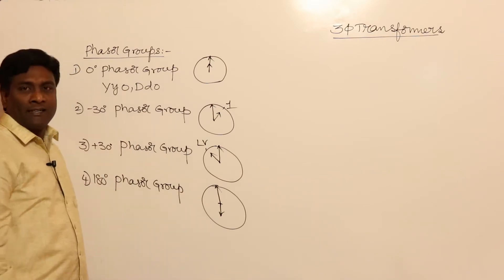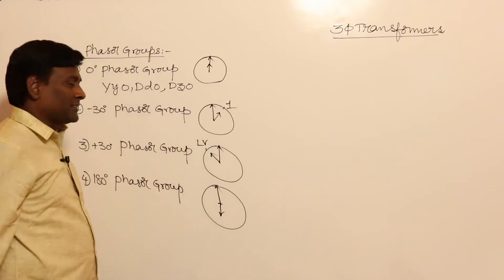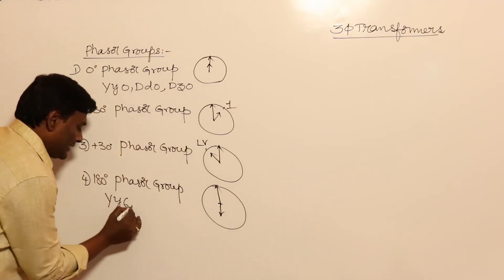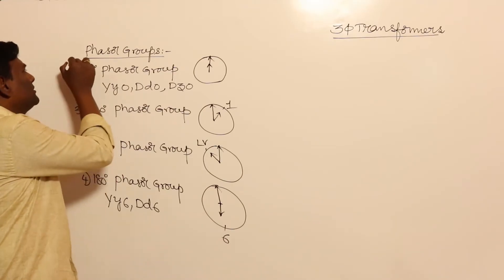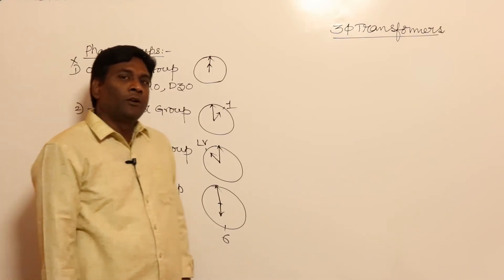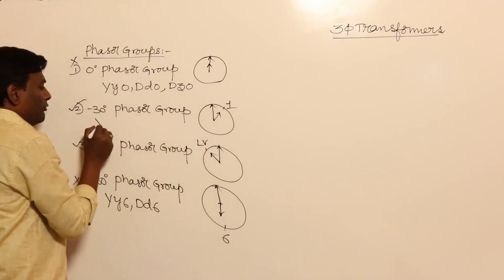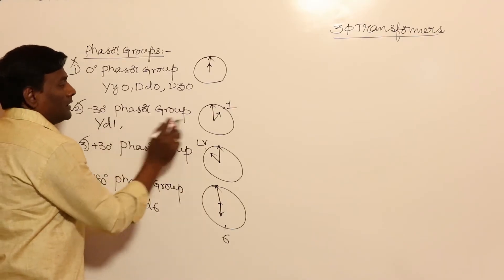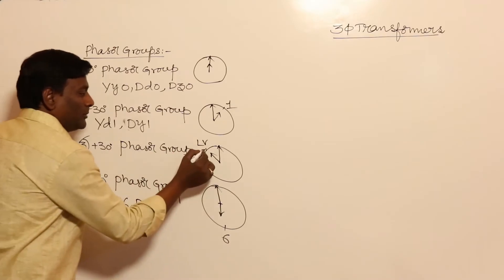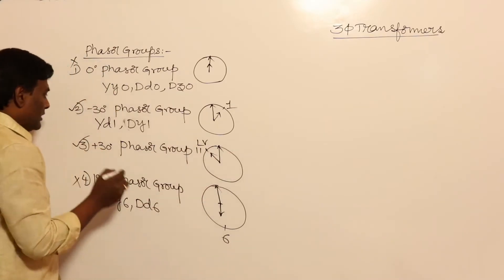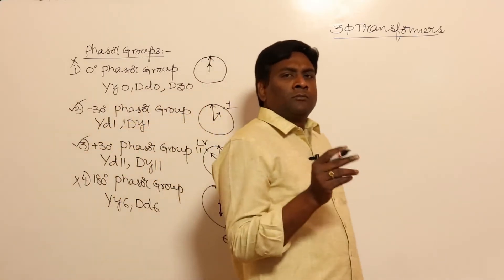For 0 degrees phasor group, YY0, DD0, and DZ0 (delta zigzag interstar) are possible. For 180 degrees, YY6 and DD6 come. In our GATE exam, these are almost 100% sure not to come — questions will come only from minus 30 or plus 30 degrees. Minus 30 degrees means YD1 and DY1 are possible; plus 30 degrees means YD11 and DY11 are possible.